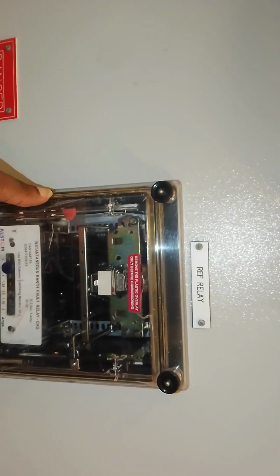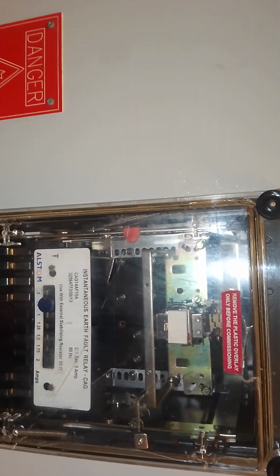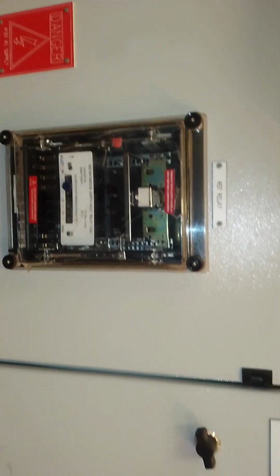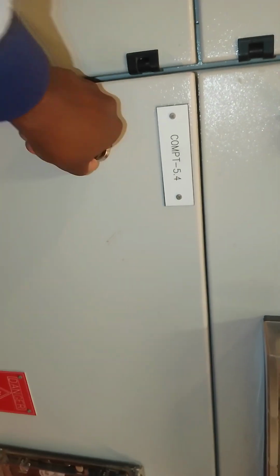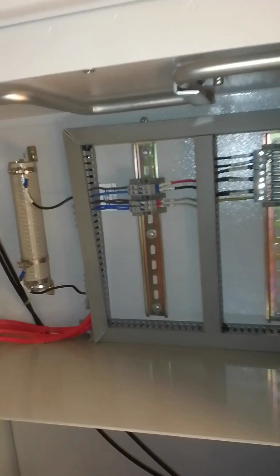This is a relay. As you can see, it's written instantaneous earth fault relay. That's why you see it's written REF. So this is our relay. If there is a problem with earthing, it will automatically sense and it will switch off all the system. We have this one from the generator, and we have this one from the power supply company, which are all connected to this coil. This is our resistor.